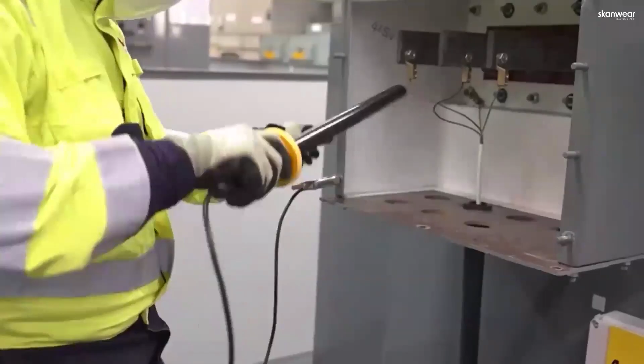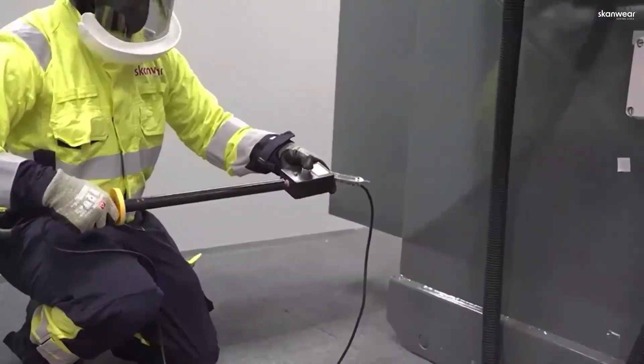We're then going to do our live-dead-live check using a voltage source, proving dead with an absence of voltage check at those conductors, and then proving our instrument again afterward. Happy with that.